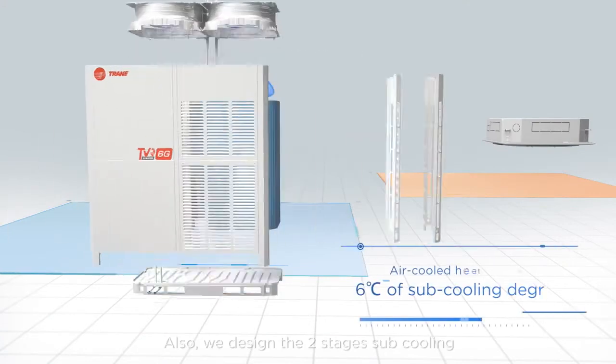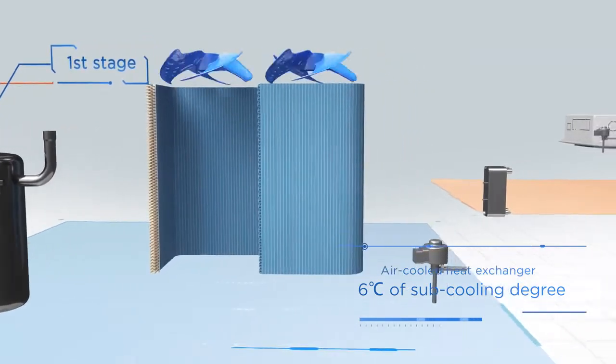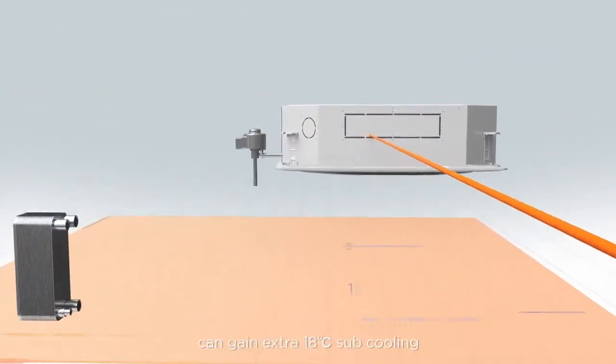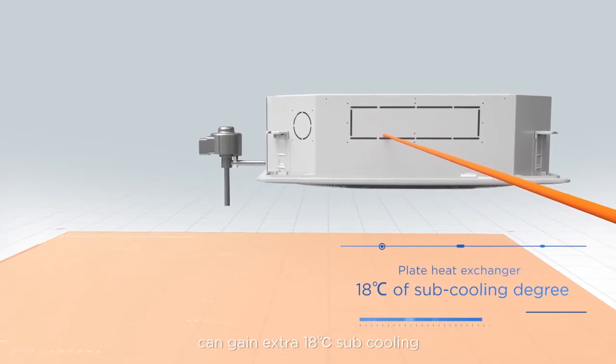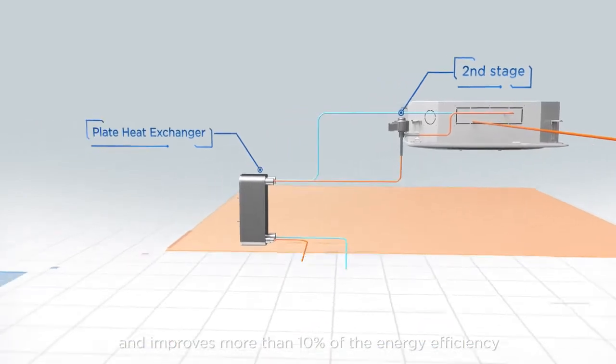Also, we designed the two-stage sub-cooling to optimize refrigerant circuit. Plate heat exchanger as a secondary intercooler can gain extra 18 degrees Celsius sub-cooling and improves more than 10% of the energy efficiency.